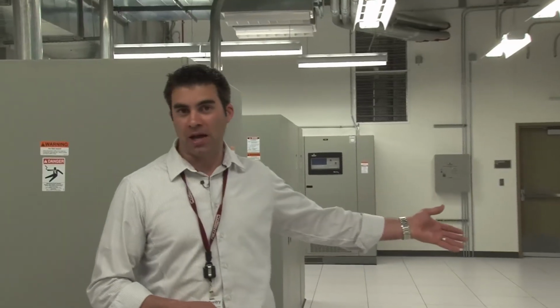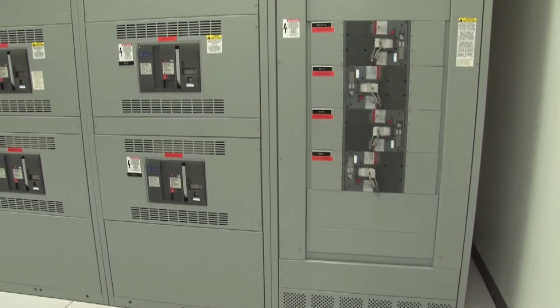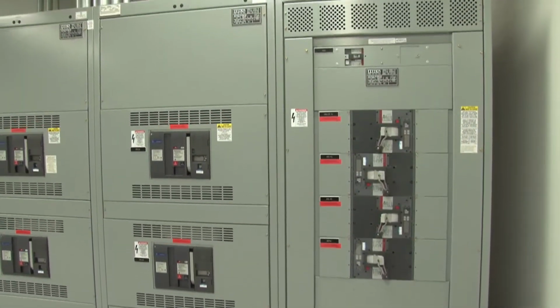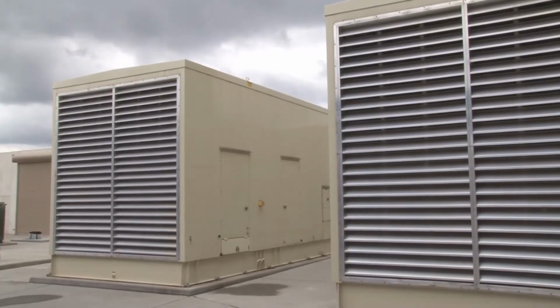In the 4,000 amp entrance is also a paralleling gear. The paralleling gear is located inside the gear where it ties us in with being able to sync with generators to utility to do a seamless exchange of power. We have 2 generators on site. One's a 2.5 megawatt and one's a 2.25 megawatt generator. Each generator has enough fuel capacity to run for 3 days at full load.